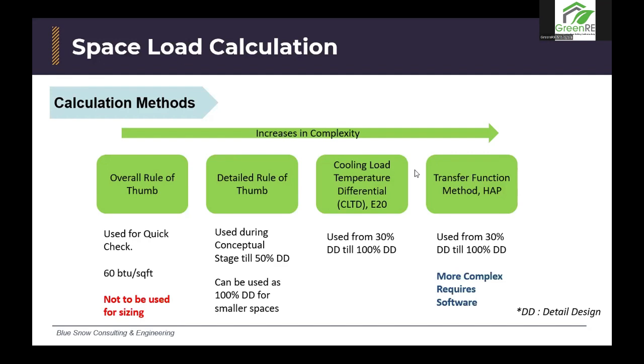The first one is the overall rule of thumb. This is often like 60 BTU per square feet of area. This is not meant to be used for sizing of the equipment. So when do you use this overall rule of thumb? Let's say the owner has an idea. He says, I want to build a shopping complex of this many square feet. I just need an overall very high level budgetary estimate on what my system may look like in terms of just capacity. That's when you can use this. So this is meant for a very high level sanity check kind of exercise.